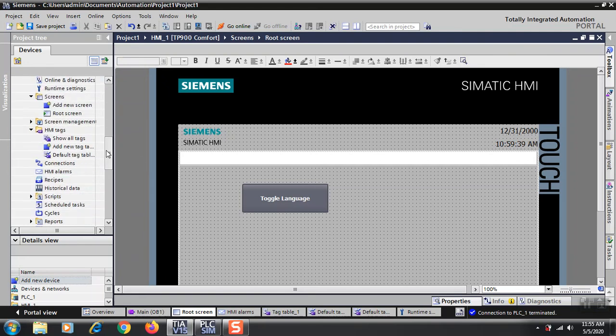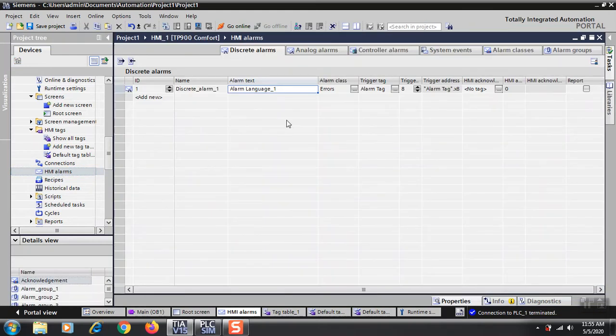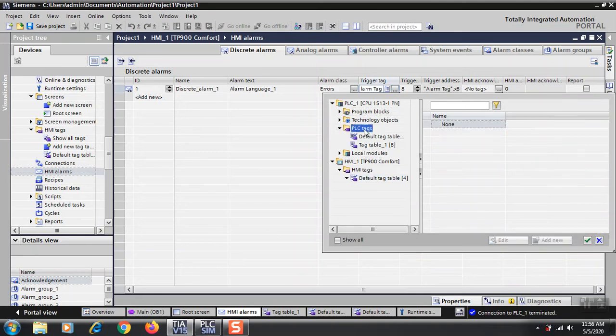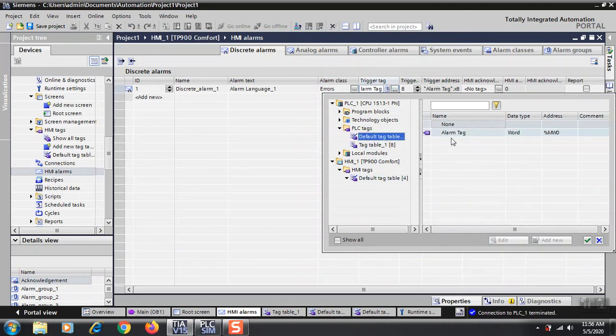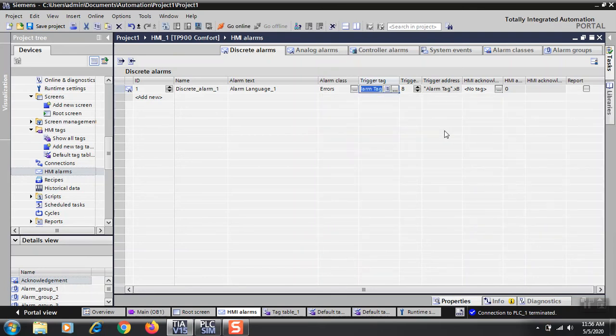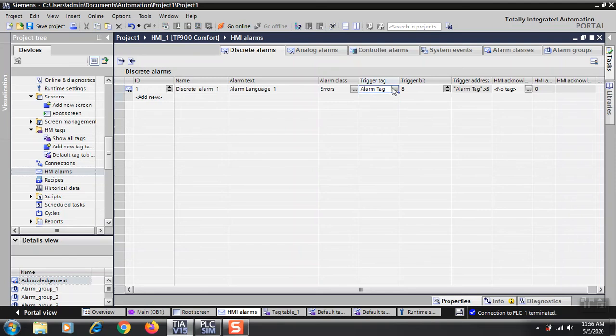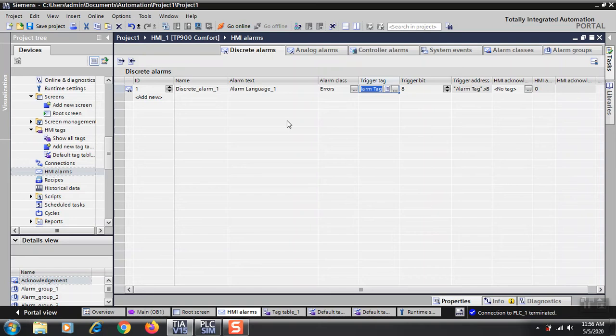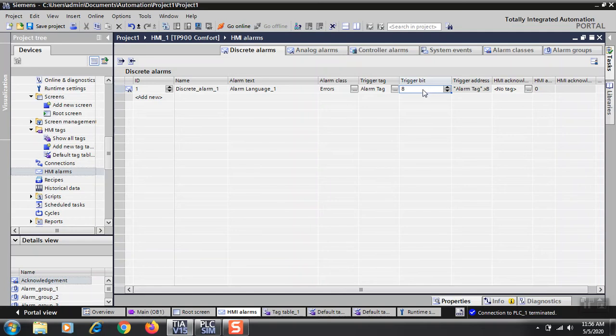Now you can go to this section HMI Alarms. You will select a trigger tag. This trigger tag refers to the PLC tag which I have put over here, MW0. Generally it is little-endian, but this is big-endian. That means your trigger bit should be at position 8. Your first byte would be MB0 from the left, and to the right it would be MB1. So the trigger bit would be 8.